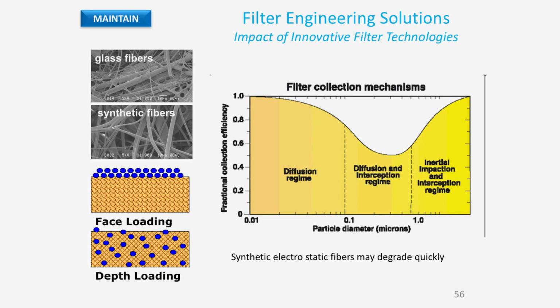And slide 56 demonstrates some of the filter theory, where the very small particles are removed and the very large particles, those greater than 1 and those less than 0.01, are removed with greater efficiency. Why? Because impaction, diffusion, and interception are all part of how filter theory really works to capture those particles.